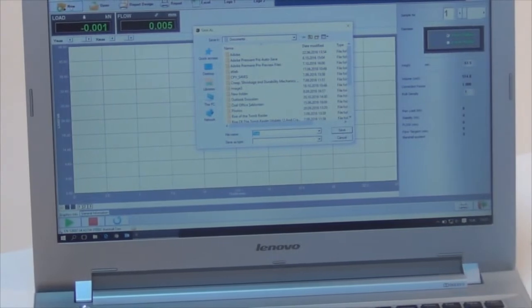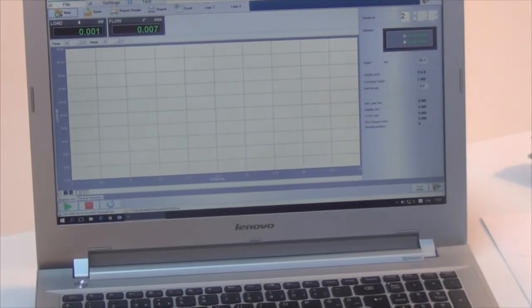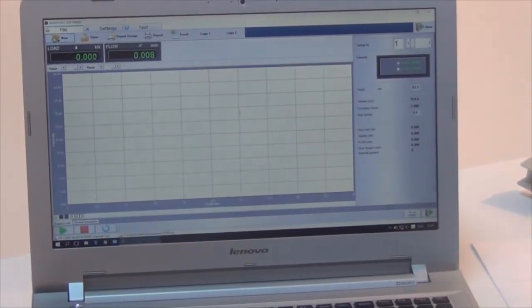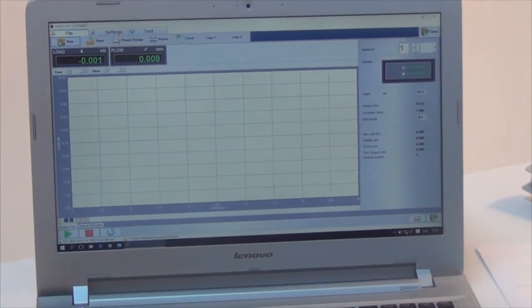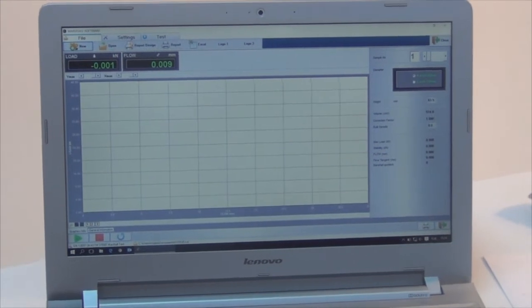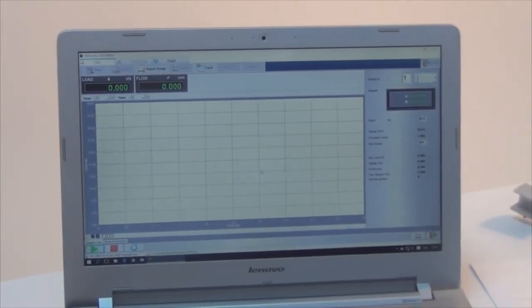You write a name according to the sample you are using. You can make three samples in one program and take the average of the readings. You can write some parameters like the height of the sample and they will be calculated automatically. Just like the other one, you press the play button and the test will start.